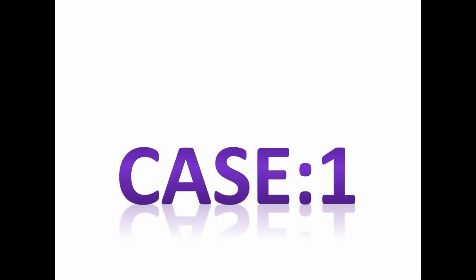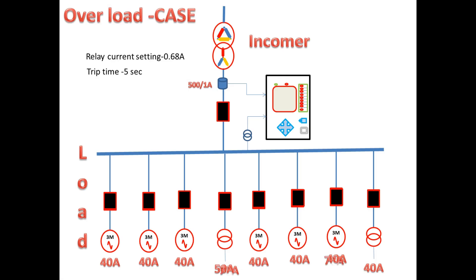Case 1: we consider all the feeders running in full load condition. Suddenly two feeders got overload, one transformer and one motor. Due to this, load current increases and reaches 380A. In this case the incomer should give chance to these two outgoing feeders. They should trip first or their load should be normalized.